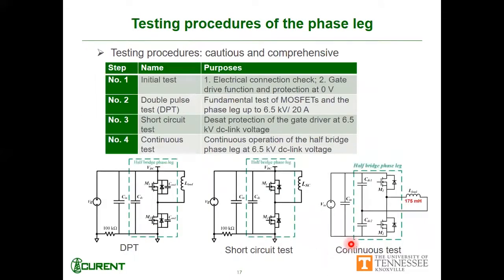So how do we validate the design phase? We have developed very systematic and comprehensive testing procedures for the phase leg, and the devices are pretty expensive, so we don't want to damage them, so we are very cautious. Basically we do it step by step. It has DPT, short circuit test, and continuous test.